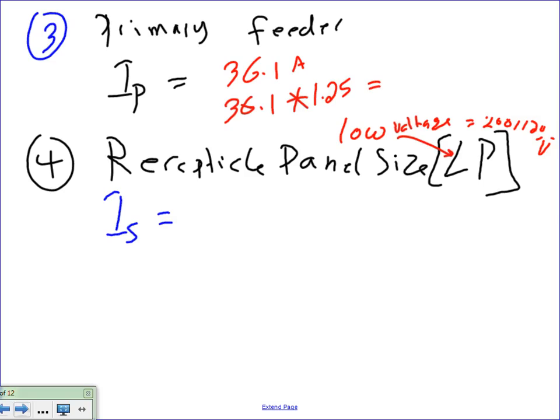Chris, what is this one for? Continuous load, 1.25. Okay, I didn't do the math. I need somebody to do the math for me here. What's 1.25 times 36.1? That will get me 45.1 amps. Okay, so you got 45.1 amps. I just multiplied it by this because I assume it's continuous.